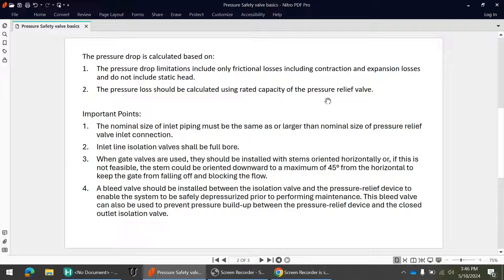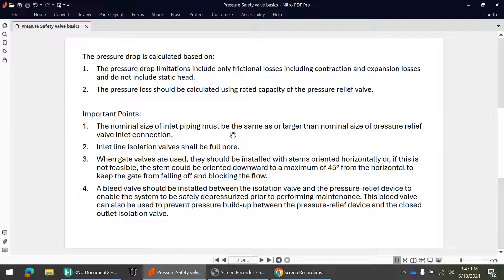Some important points: the nominal size of the inlet piping should be at least equal to the inlet flange size of the PSV. For example, if you have selected a PSV 3K4, which means the inlet flange is 3 inch and outlet is 4 inch, the inlet line should be at least 3 inch. You cannot select a 2-inch line for a PSV that has a 3-inch inlet nozzle, even if it still meets the 3% pressure drop criterion.